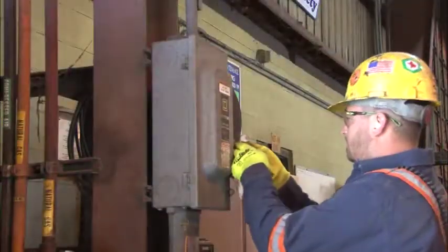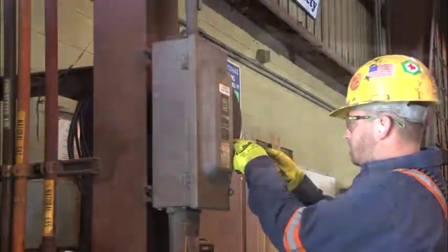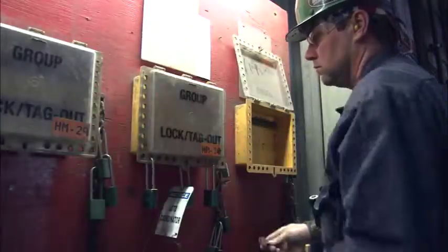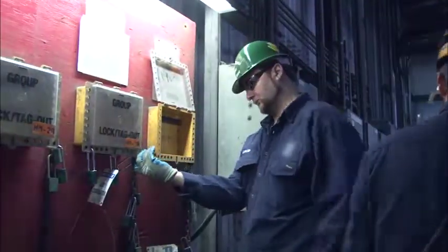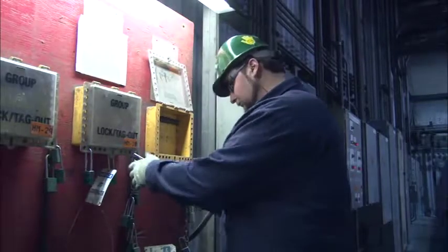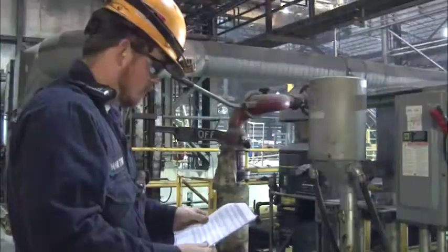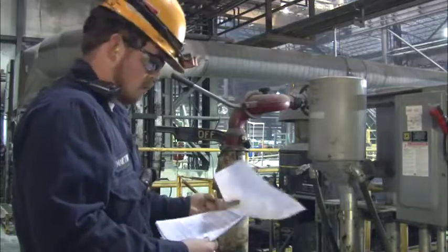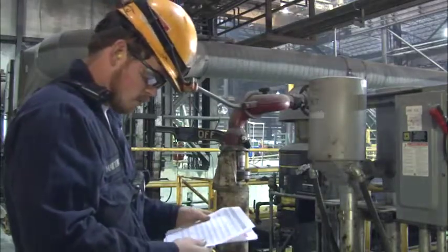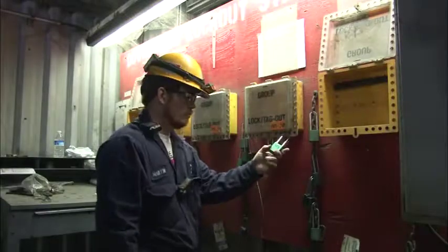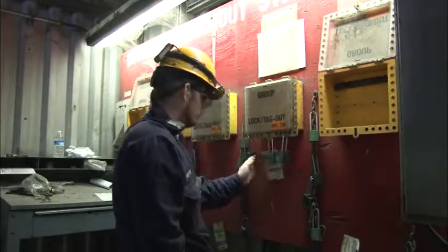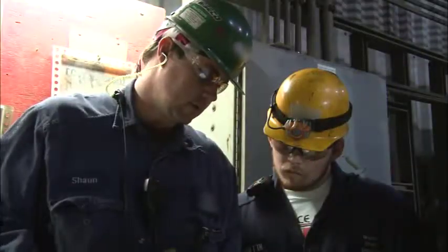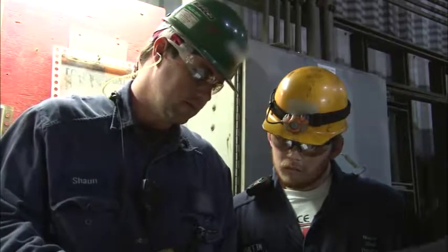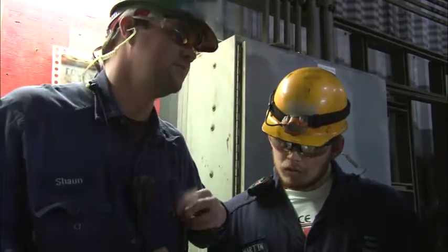Once all energy sources have been identified and properly locked out per the energy control procedures, the authorized employee places the keys to the lockout devices in a lockbox. The employees performing the servicing or maintenance work must then affix their personal locks to the lockbox. This enables the employees to ensure their protection and inform others that employees are working on the equipment. As long as personal locks remain attached, the authorized employee in charge of the group lockout knows that the work has not been completed and that it is not safe to re-energize the equipment.